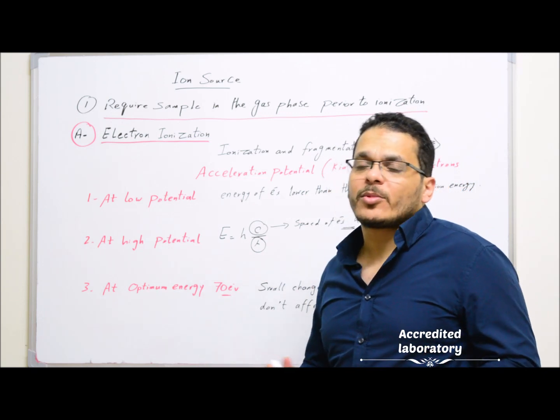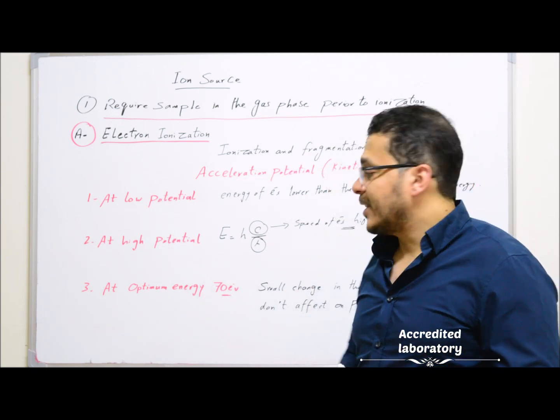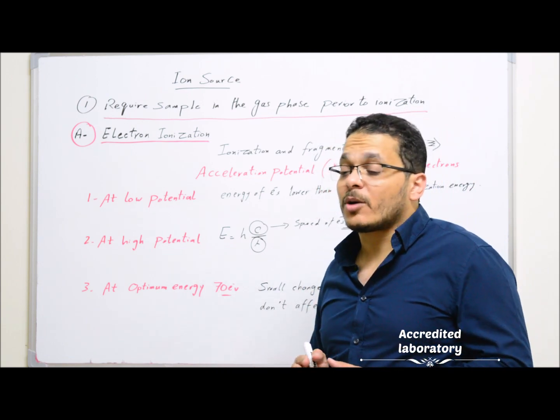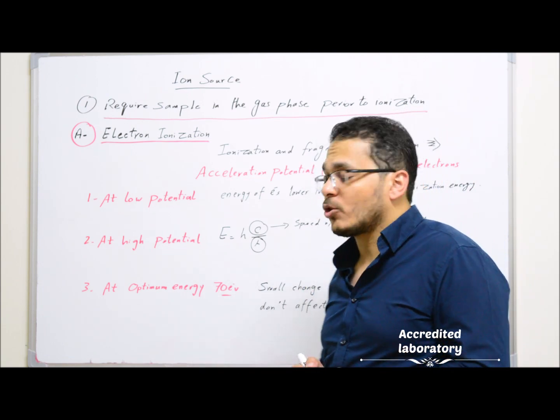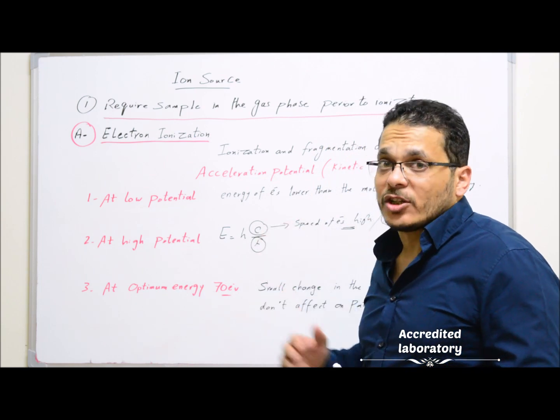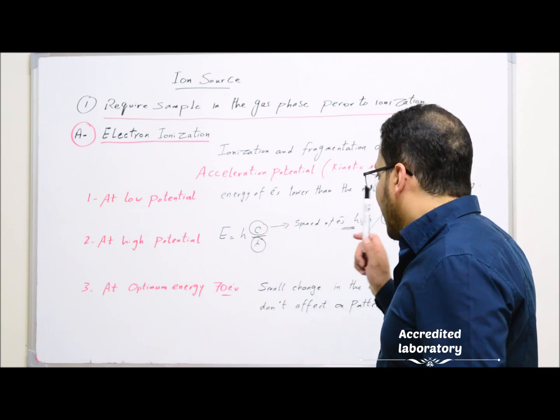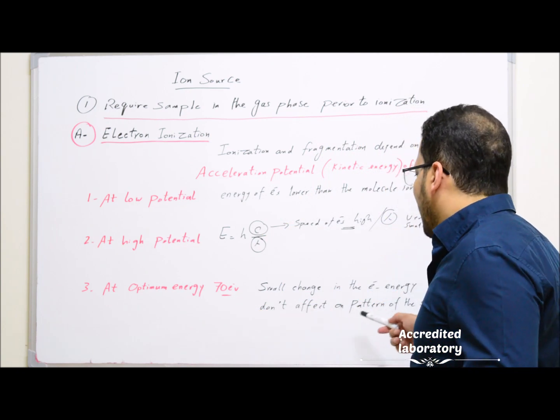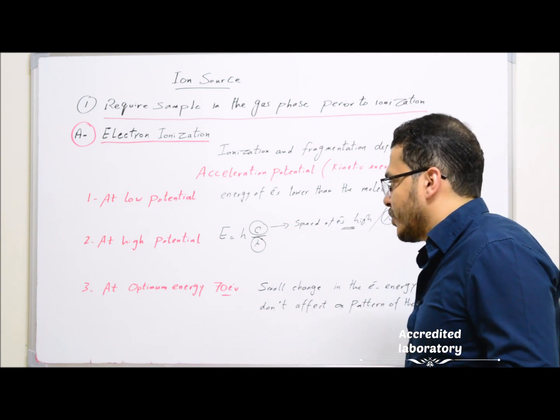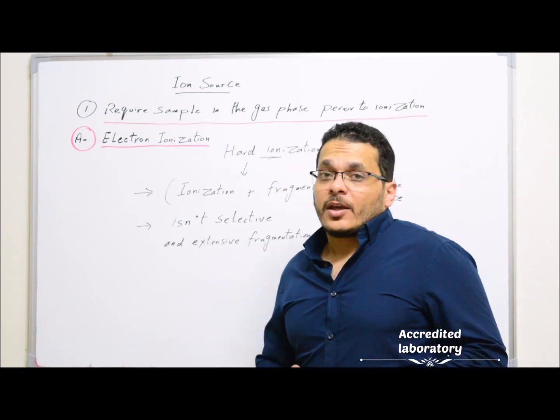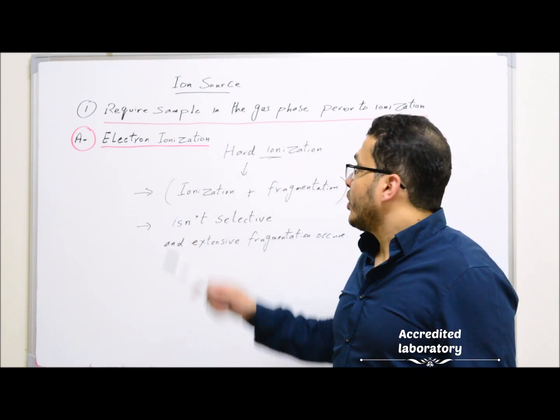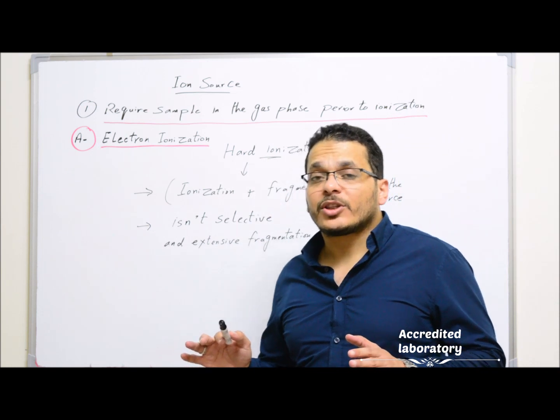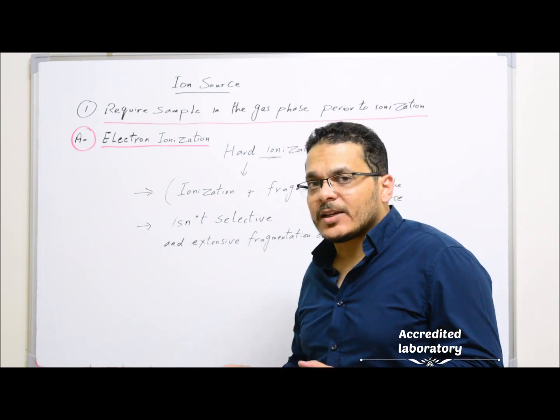At 70 electron volts, which is the optimum energy, only sufficient energy can be transferred to overcome the ionization potential of most organic compounds, and ionization of molecules will happen. Also, a small change in electron energy will not affect the pattern of the spectrum. Electron ionization is considered to be hard ionization because ionization and fragmentation both take place inside the ion source.